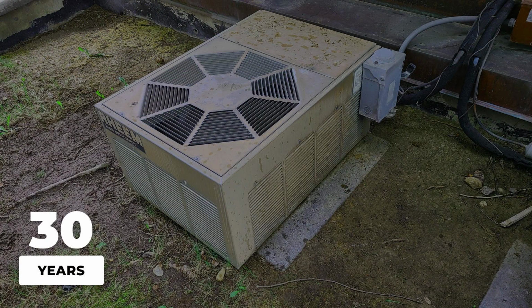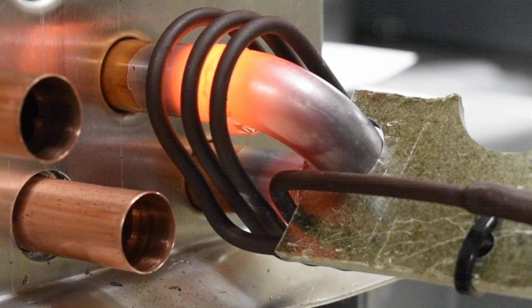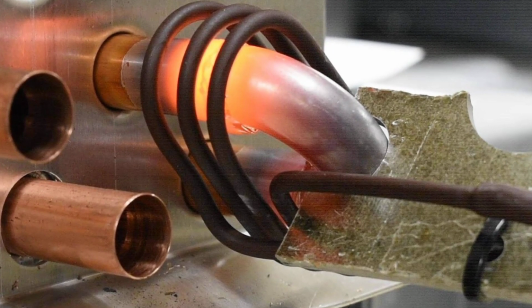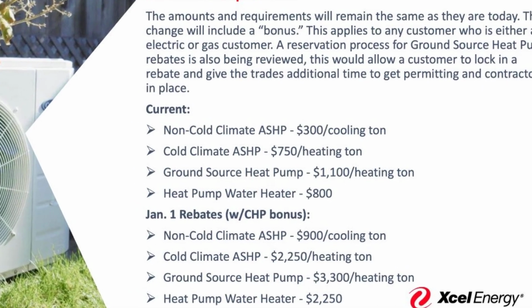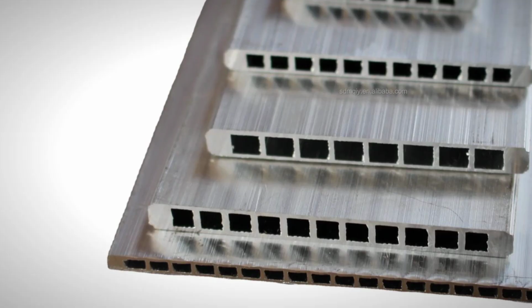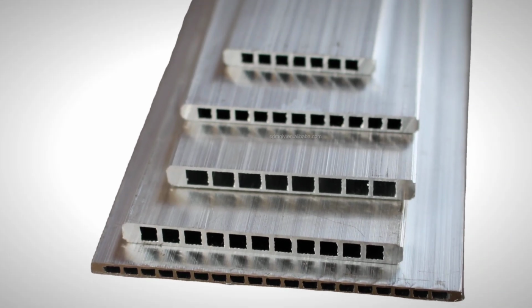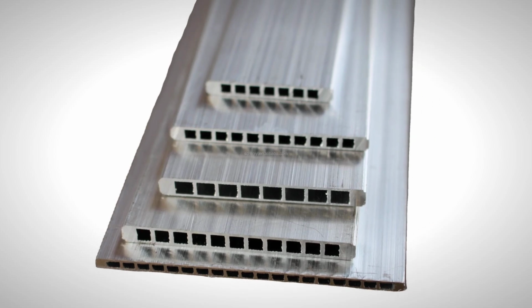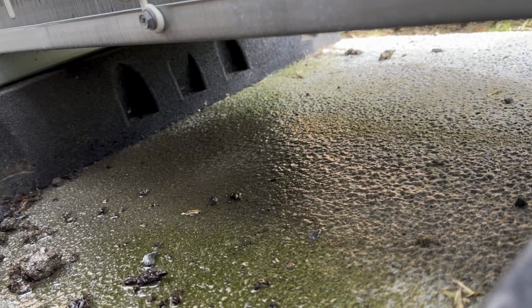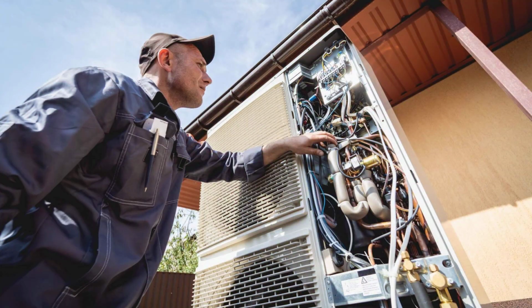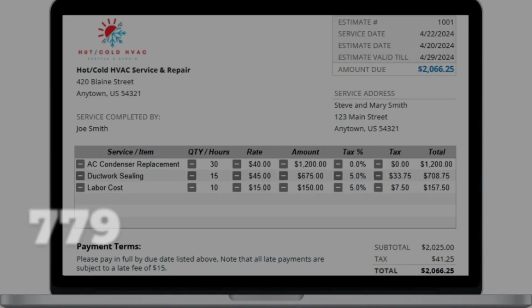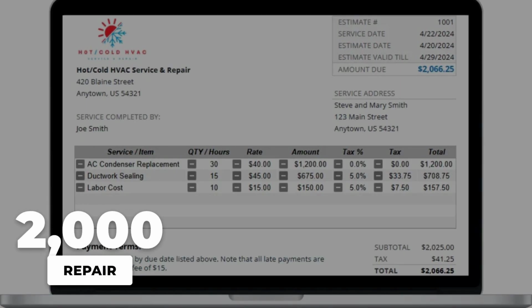The heat pump your parents bought lasted 20 to 30 years. With a brazeable copper coil, a technician could fix it in an afternoon. The heat pump you bought, the high-efficiency one the rebate program pushed, uses an all-aluminum microchannel coil borrowed from automotive radiators. Compact, efficient on a test bench, and when it leaks, the manufacturer's own service bulletin calls the field repair temporary. Coil replacement runs $600 to $2,000.